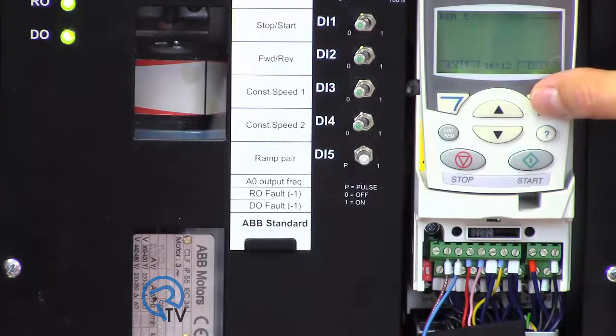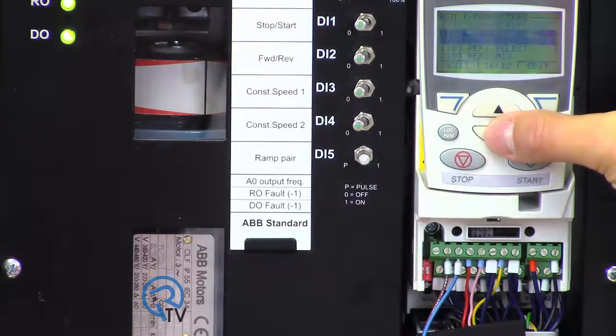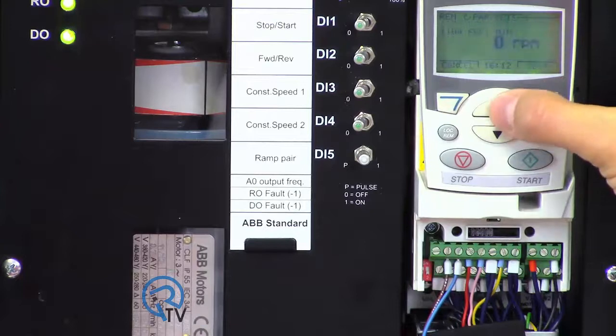To adjust the speed reference based on these limits, use the keypad to navigate to reference select group 11. Parameter 1104 changes to 200 RPMs. Parameter 1105 changes to 1400.